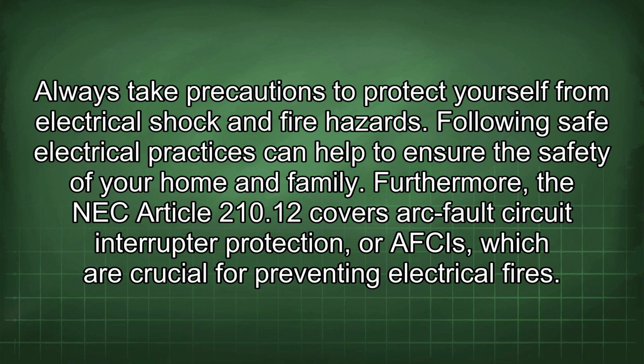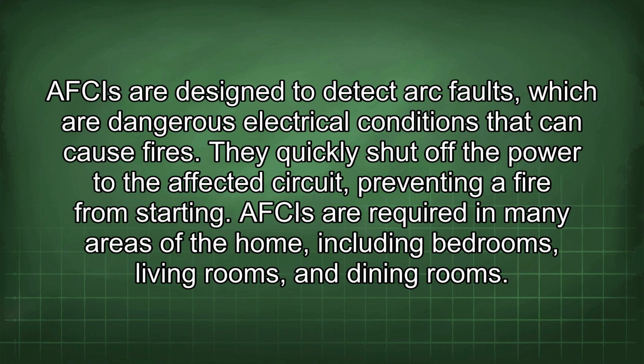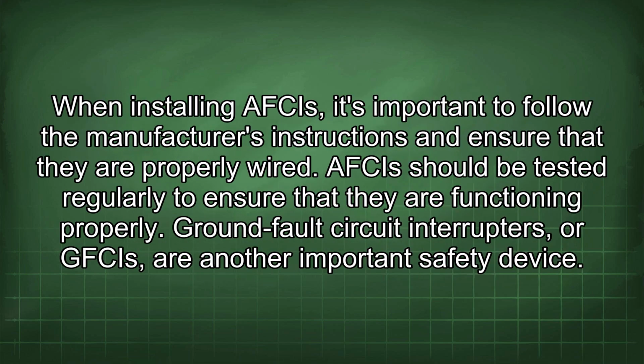Furthermore, the NEC Article 210.12 covers arc fault circuit interrupter protection, or AFCIs, which are crucial for preventing electrical fires. AFCIs are designed to detect arc faults, which are dangerous electrical conditions that can cause fires. They quickly shut off the power to the affected circuit, preventing a fire from starting. AFCIs are required in many areas of the home, including bedrooms, living rooms, and dining rooms. When installing AFCIs, it's important to follow the manufacturer's instructions and ensure that they are properly wired. AFCIs should be tested regularly to ensure that they are functioning properly.